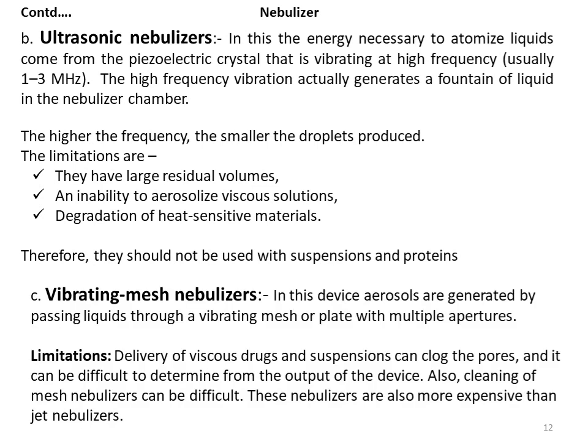Next is vibrating mesh nebulizers. In this device, aerosols are generated by passing liquids through a vibrating mesh or a plate with multiple apertures. However, these devices also have limitations: delivery of viscous drugs or suspensions can clog the pores; it can be difficult to determine the output of the device; cleaning of the mesh nebulizers can be difficult; and these nebulizers are more expensive than jet nebulizers.